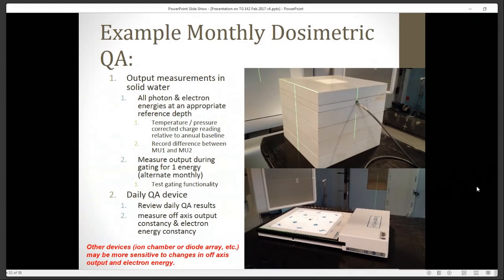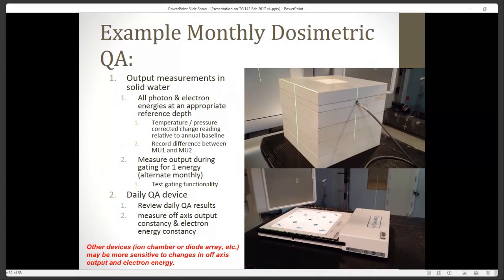For monthly dosimetry: start with output measurements in solid water with temperature/pressure correction, get a charge reading relative to an annual baseline at an appropriate depth. Also measure output during gating for one energy — alternated monthly — getting integrated charge with and without gating. Then run the daily QA device, review daily QA results, and measure off-axis output constancy and electron energy constancy, using either the daily QA device or another device with better resolution.